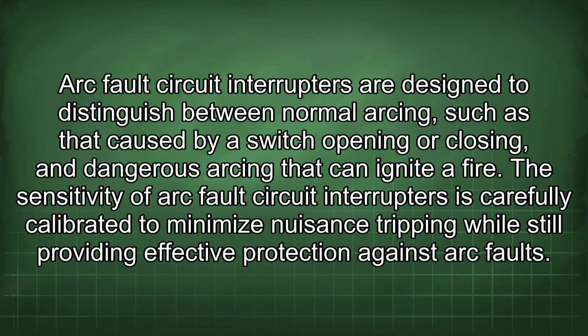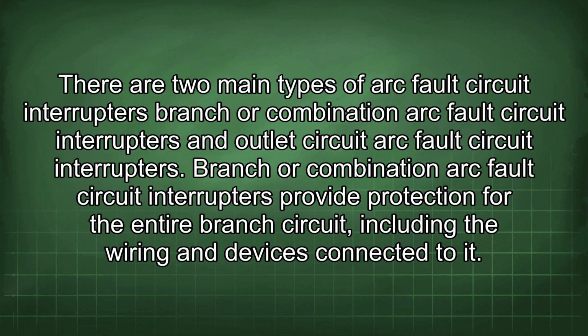Arc fault circuit interrupters are designed to distinguish between normal arcing, such as that caused by a switch opening or closing, and dangerous arcing that can ignite a fire. The sensitivity of arc fault circuit interrupters is carefully calibrated to minimize nuisance tripping while still providing effective protection against arc faults. There are two main types of arc fault circuit interrupters: branch or combination arc fault circuit interrupters and outlet circuit arc fault circuit interrupters.